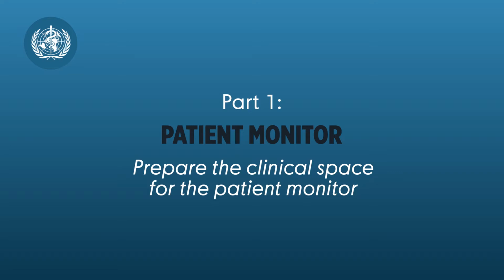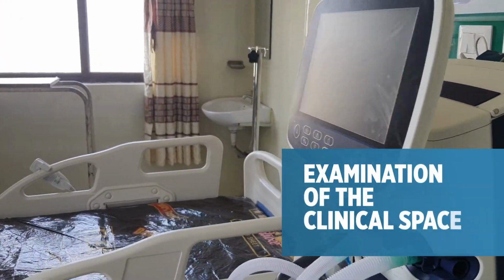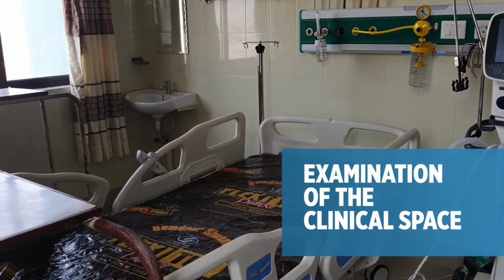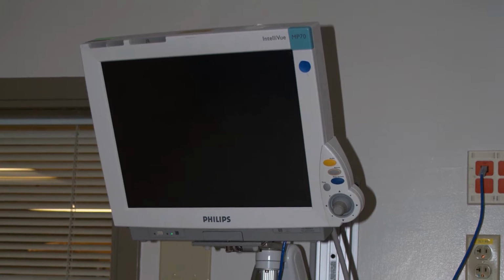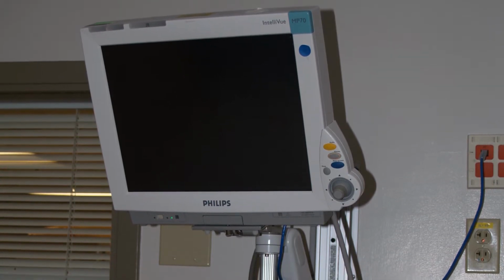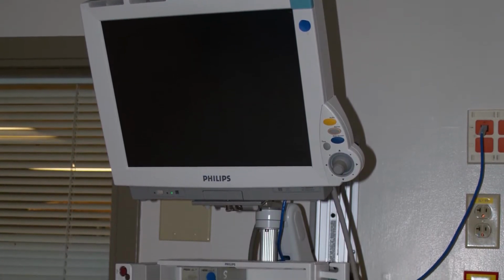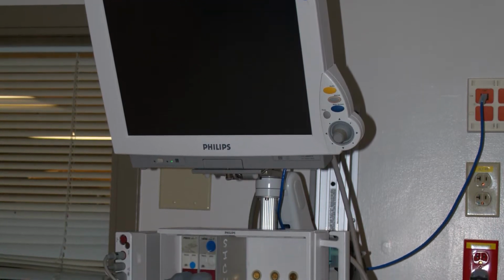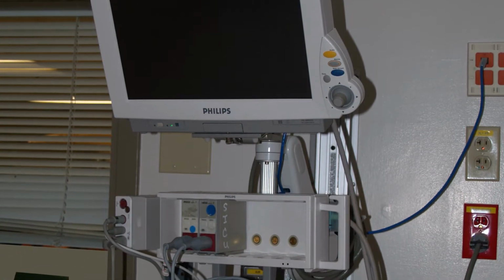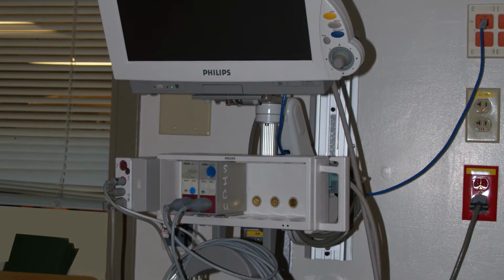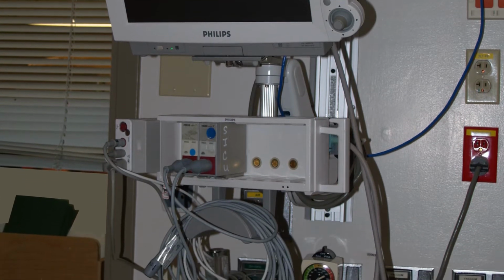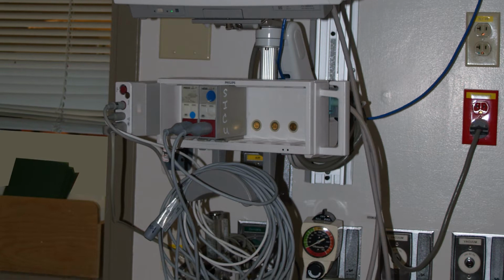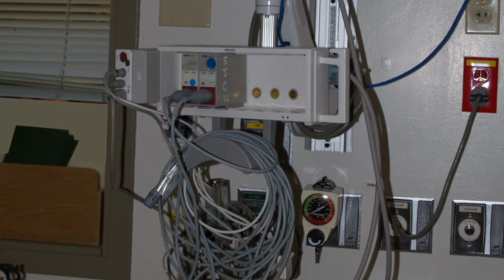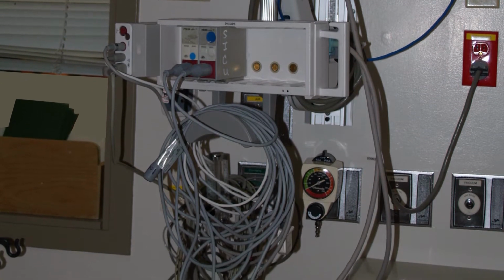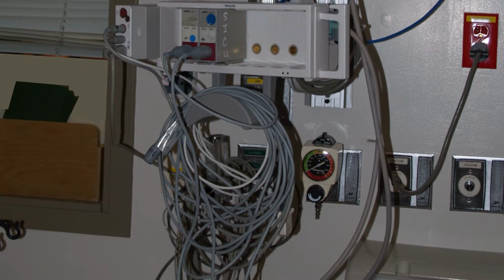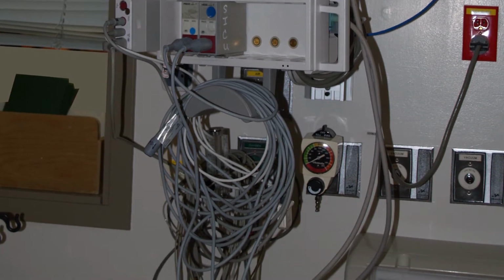Before your new patient monitor arrives, it is important to confirm that the clinical space it will be used in is ready for it. Several aspects of the clinical space will need to be examined. Determine if the device will be mounted permanently in the clinical ward. Make arrangements with the proper party to install permanent mounting for the device which meets the needs of clinical staff, is within 1.5 meters of an appropriate electrical outlet, is safely installed to meet the weight and usage requirements of the device, and has proper communications connections should a central station or computer connection be required.